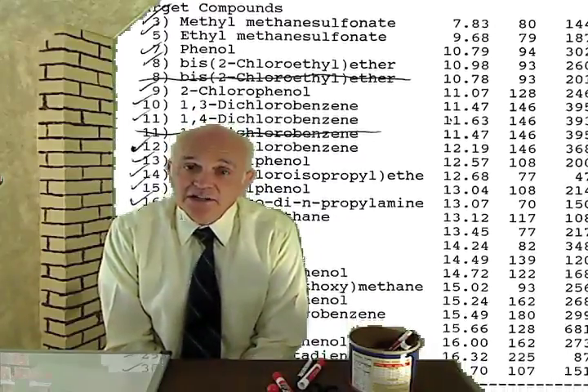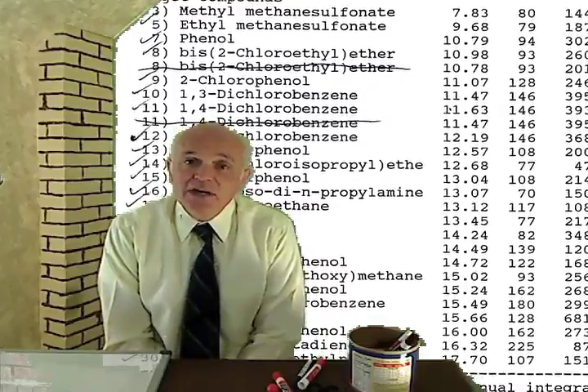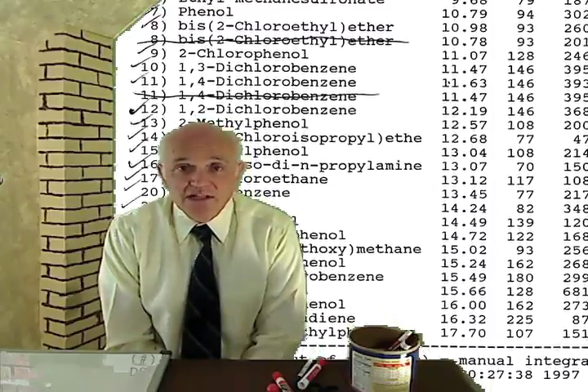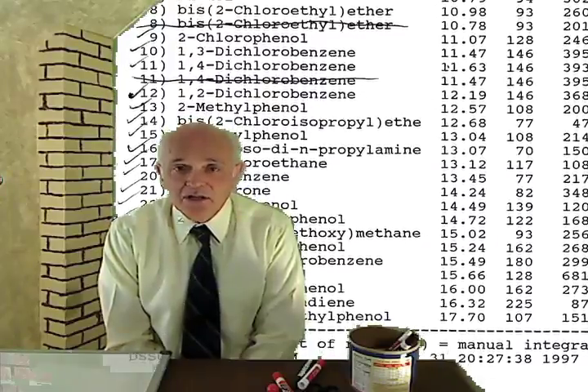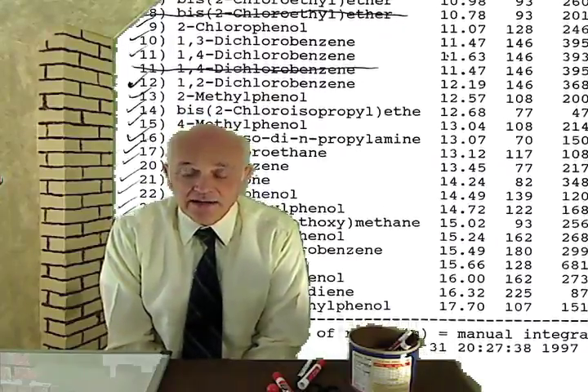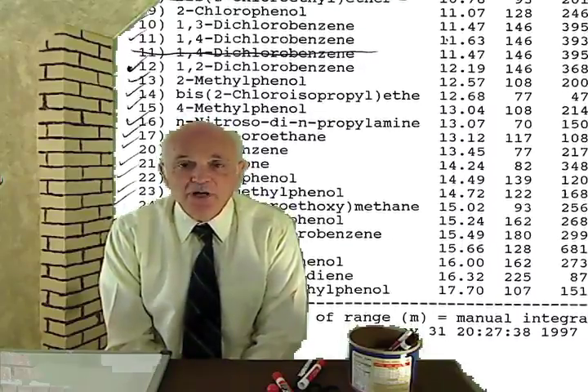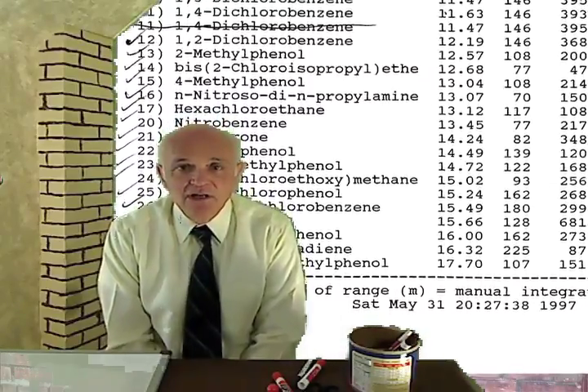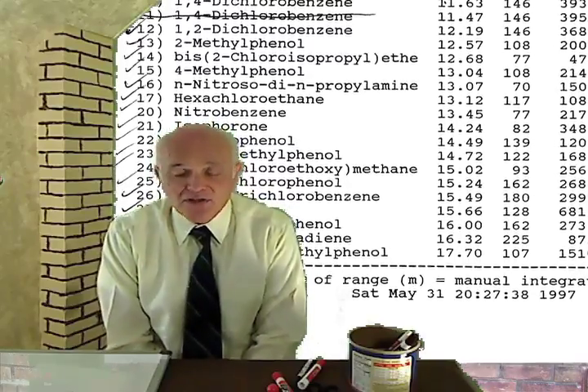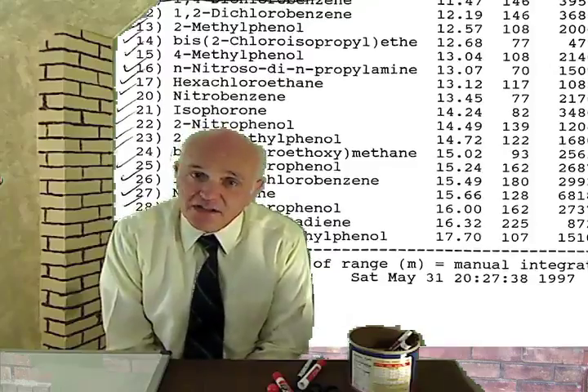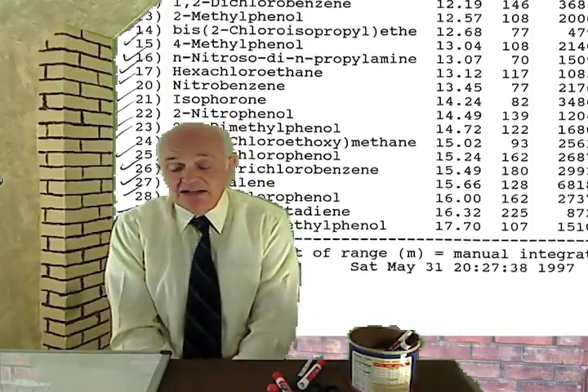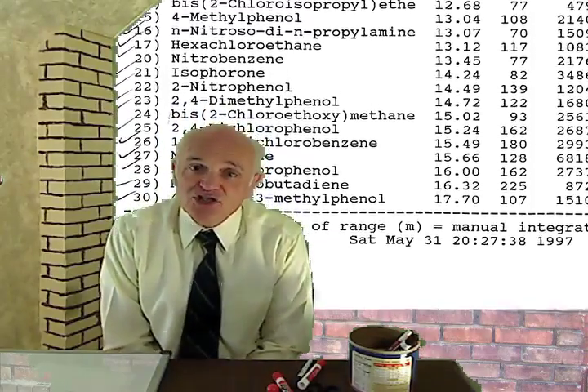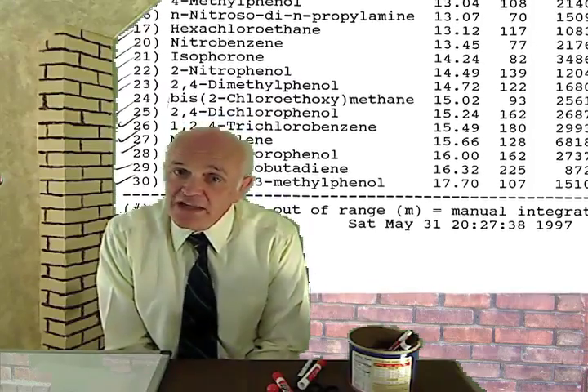Let's say you have a sample from the Walmart site and it comes up clean — the soil or water is clean. How do you know the mass spec didn't stop running? Maybe the quadrupole fried and nothing happened. Maybe the injection didn't work, or the extraction didn't work. There are a lot of steps, a lot of things that can go wrong. You get zero — well, that's nice. But you've got to know for sure that the analysis worked the way you think it did.